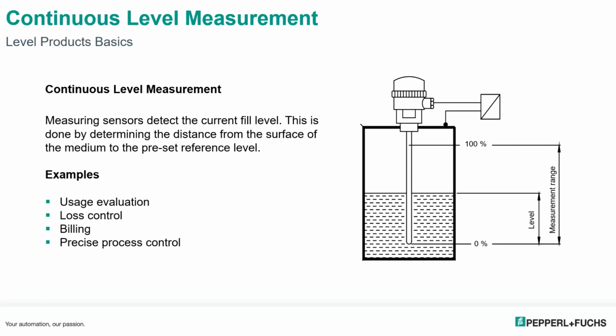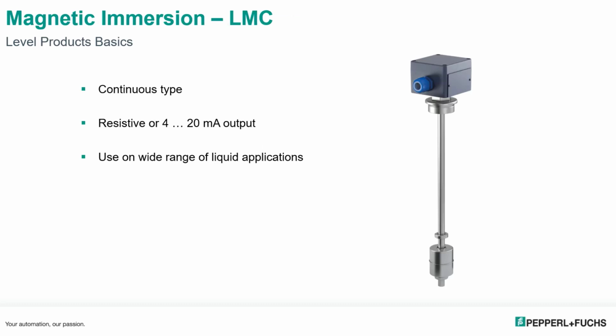Also loss control. They can tell when you're losing something, for billing purposes and for precision process controls for medium intake and outtake. The magnetic immersion probe, the LMC, is a continuous type. Unlike the LML, which is a limit, the LMC gives you the continuous type output. There are little reed switches all the way along that rod version. It gives you either a resistive output or a 4 to 20 milliamp output, and they can be used for a wide range of liquid applications.